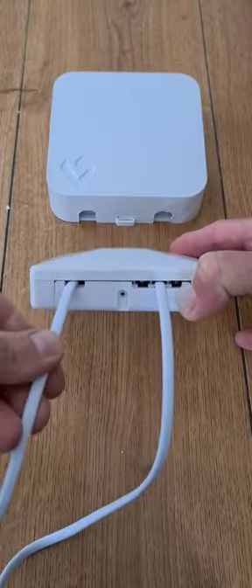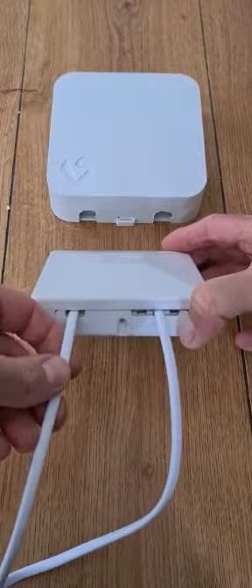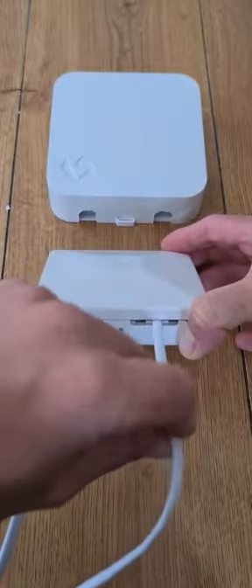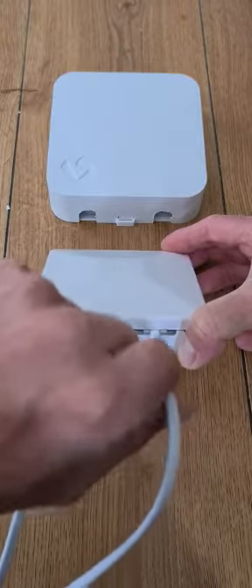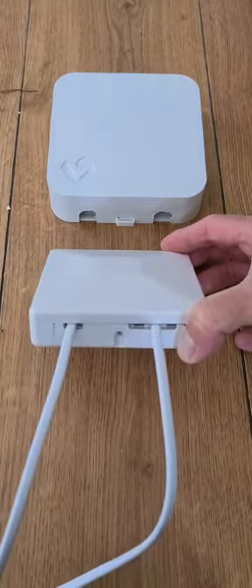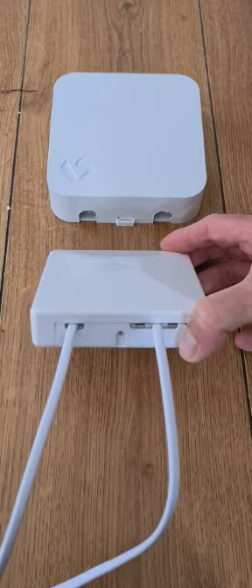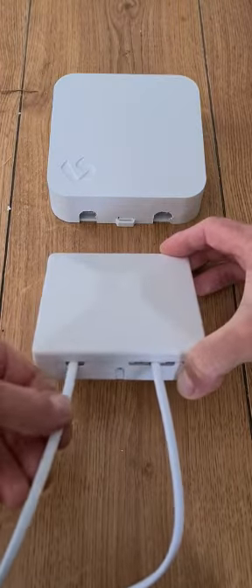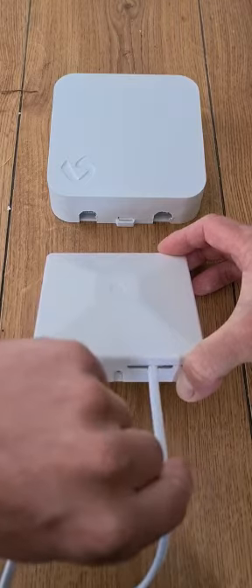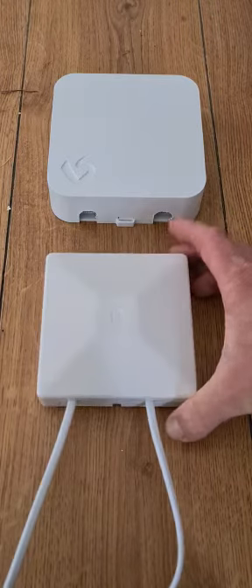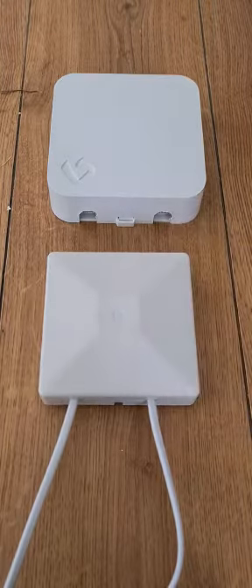This cable on the left here, as you look front on, is the power cable. And this one on the right is the data cable, the bus, which is going into the boiler. It's very important that you don't get these two wires crossed. So from the front, the power cable's on the left, and the right hand cable is the data cable. It may be worth marking those up.